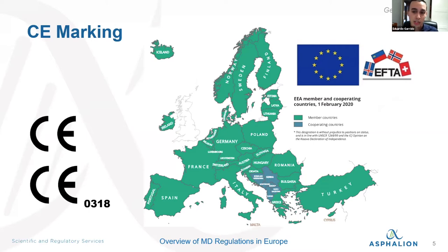In order to place your device on the market, you've got to get this CE marking. You might have seen this logo, which can go either alone or with a combination of numbers. If it goes alone, it means the manufacturer did the self-certification. If it goes with numbers, it's because it includes the number of the notified body. We'll talk about this in a second.